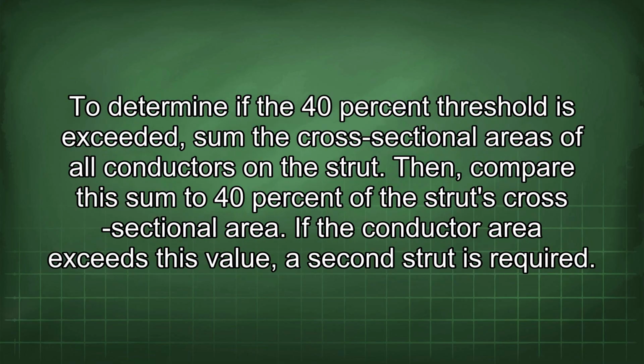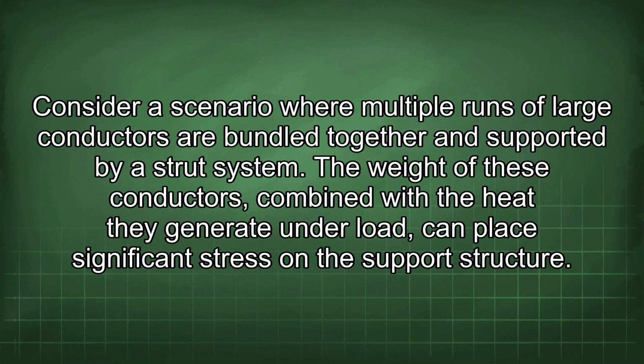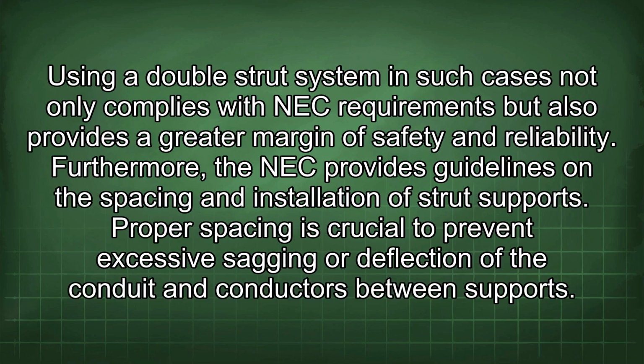To determine if the 40% threshold is exceeded, sum the cross-sectional areas of all conductors on the strut. Then compare this sum to 40% of the strut's cross-sectional area. If the conductor area exceeds this value, a second strut is required. Consider a scenario where multiple runs of large conductors are bundled together and supported by a strut system. The weight of these conductors, combined with the heat they generate under load, can place significant stress on the support structure. Using a double strut system in such cases not only complies with NEC requirements but also provides a greater margin of safety and reliability.